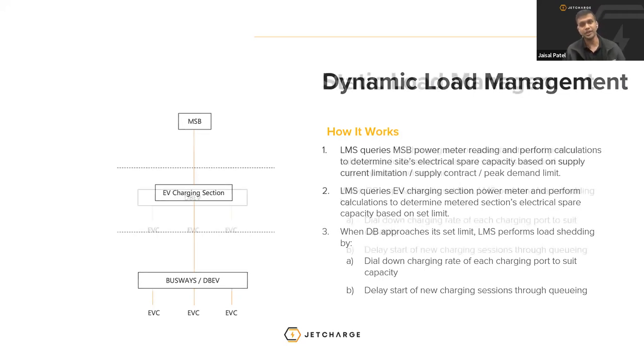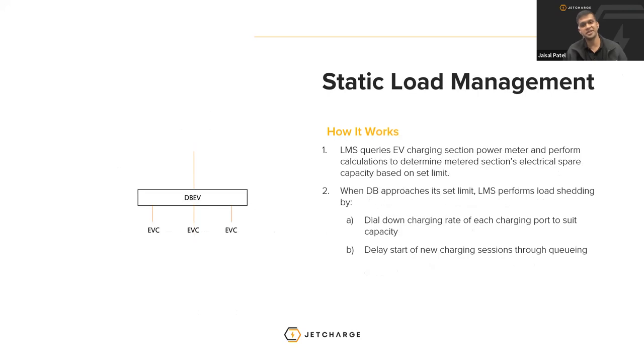Next slide. A static load management system works extremely similarly to a dynamic load management system, except you only require one reference point. So essentially there would be either a power meter on the distribution board feeding the chargers or the main switchboard. And based on the availability to the site, it won't let the distribution board approach its set limit and performs load shedding accordingly. Next slide.